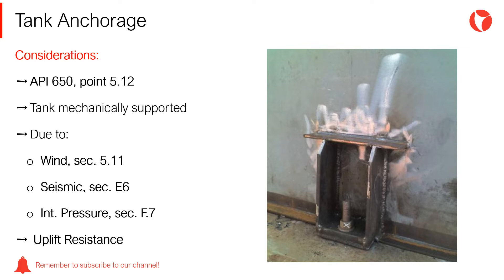Anchor bolt calculation is performed according to section 5.12 of the code. Storage tanks may need to be anchored due to the following reasons: wind (section 5.11 of the code), earthquake (sections E5.2 and E6 of the code), and internal pressure (section F7 of the code).